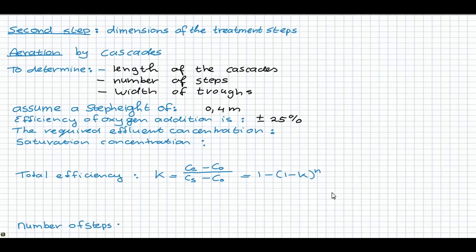Based on the required effluent concentration of, in our case, 8 milligrams oxygen per liter, and the saturation concentration that depends on temperature and partial pressure, we can calculate the total efficiency. For saturation concentration we take 11.3 milligrams per liter for a water temperature of 10 degrees Celsius. The efficiency is the desired effluent concentration minus the influent concentration of 0.5 milligrams oxygen per liter, divided by the saturation concentration minus the influent concentration. This gives an efficiency of 0.69.